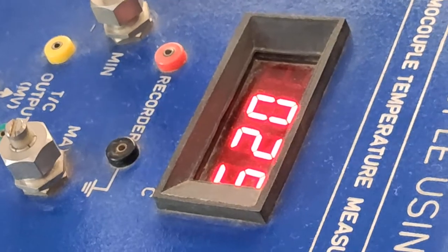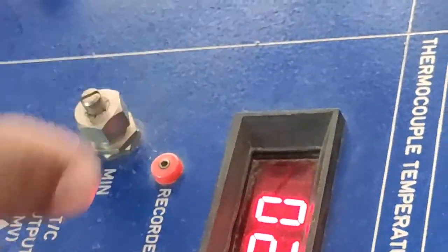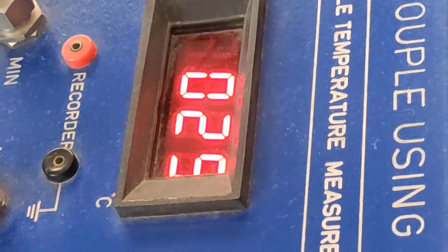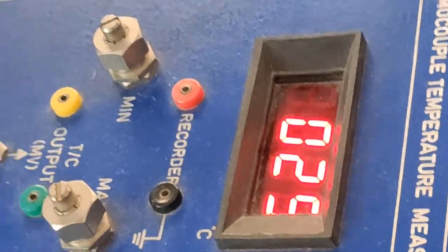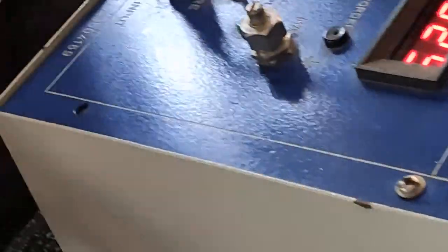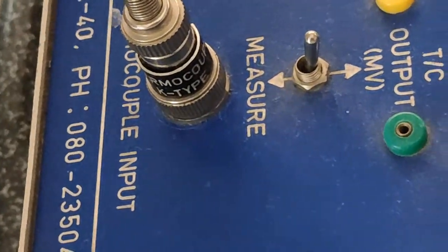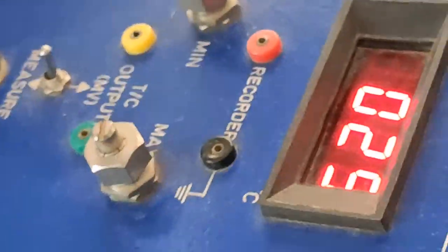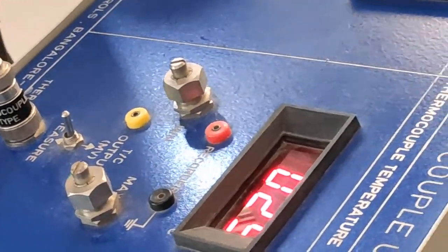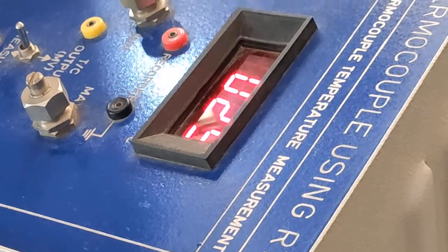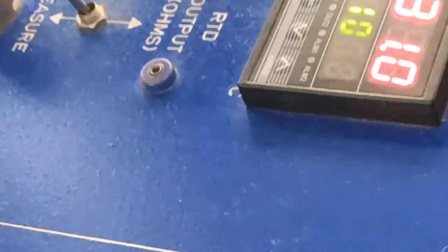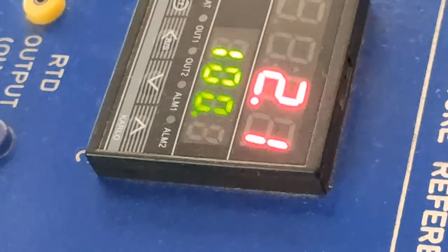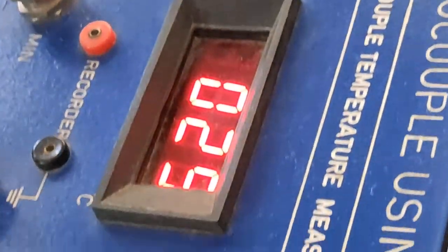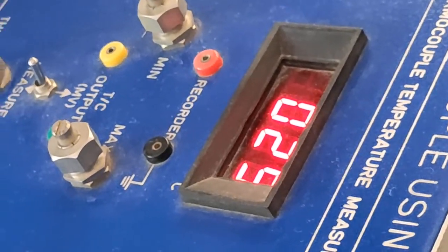As the temperature rises, for every 10 degrees of rise in RTD temperature, the thermocouple temperature is noted, and the error between the two is found. Ti is the RTD temperature and Ta is the thermocouple temperature. The difference of the two divided by Ta, multiplied by 100, gives the percentage of error. Now you can see there is a rise in the RTD temperature, whereas this thermocouple is still not sensing it, because it is not as precise as the RTD. The RTD can sense temperature better compared to this thermocouple.